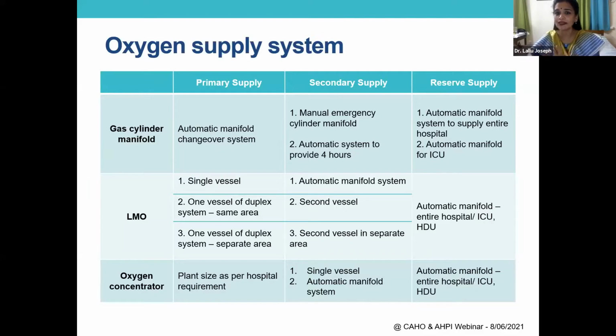And you should also have a secondary supply. That could be a manual emergency cylinder manifold, another manifold, and an automatic system to provide at least 4 hours of supply, which should certainly be there. And there should be another reserve supply, which again can be an automatic manifold in another building, or at least a separate manifold for your ICU, because that is your critical load. Only if you have this, then you have a backup to a backup to a backup.